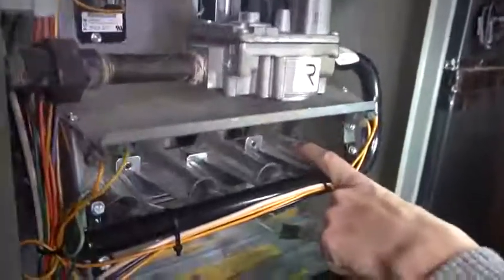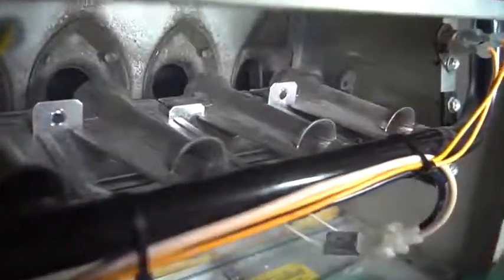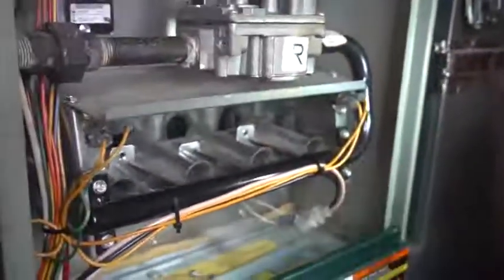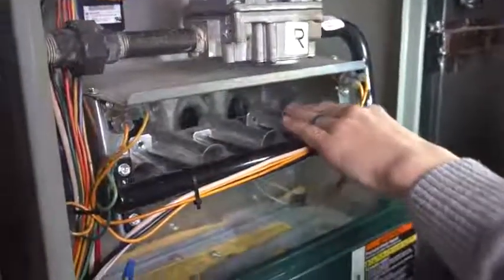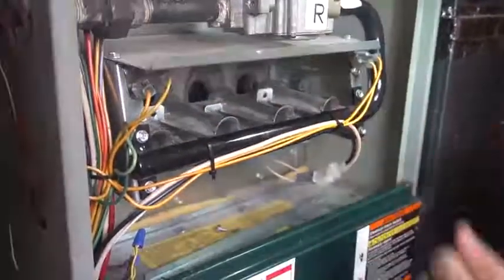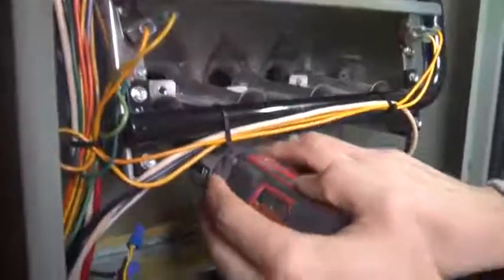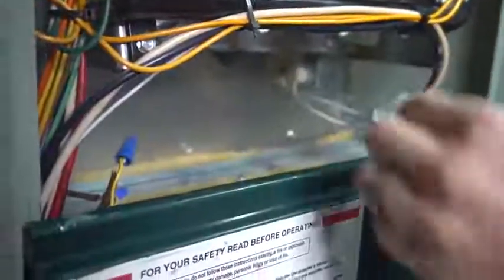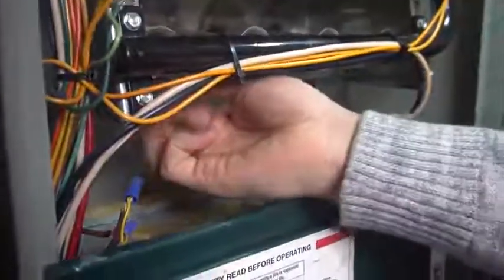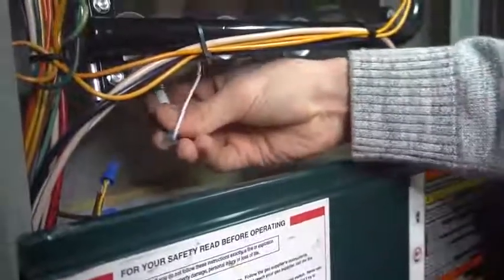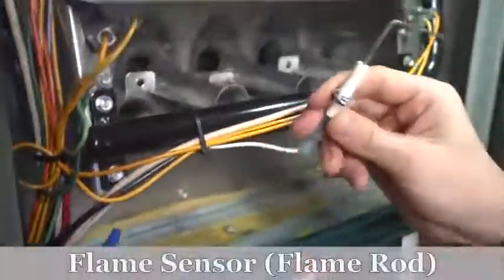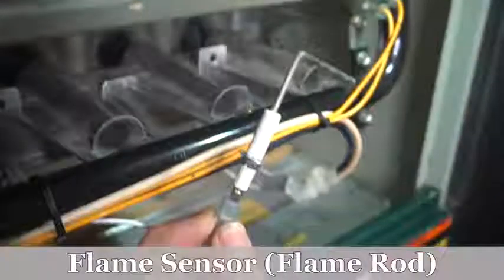The next thing on the list, the igniter starts to glow bright orange, and then that gas valve will open up and the igniter lights that gas and all the burners light. And then on the opposite side, almost every modern furnace will have one of these. On the opposite side, you have a flame sensor. The flame sensor is just a stainless steel rod.